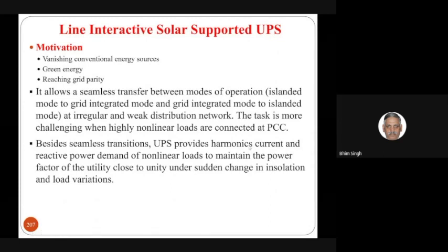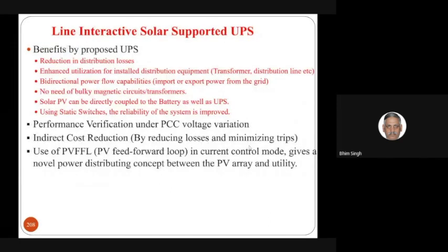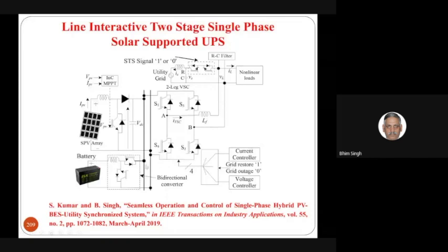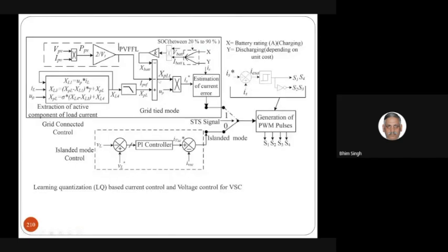Another is, of course, we can put it in a line interactive UPS kind of mode. And here, if we put the PV with the buck boost converter, we have a solar generation, we have a grid. So the grid may be there, may not be there. Still, we are able to feed the non-linear load without any problem or transition. So these are typically the controls when it is a grid interface system.